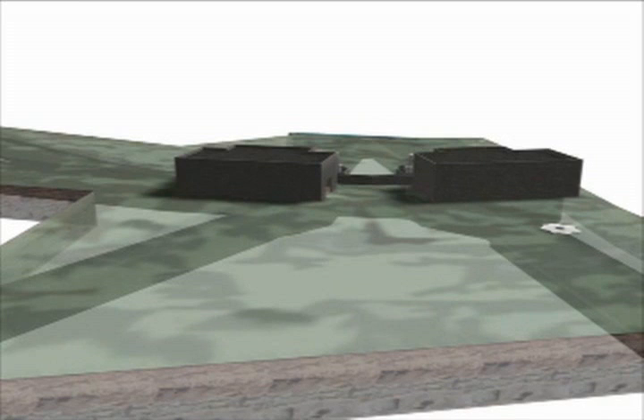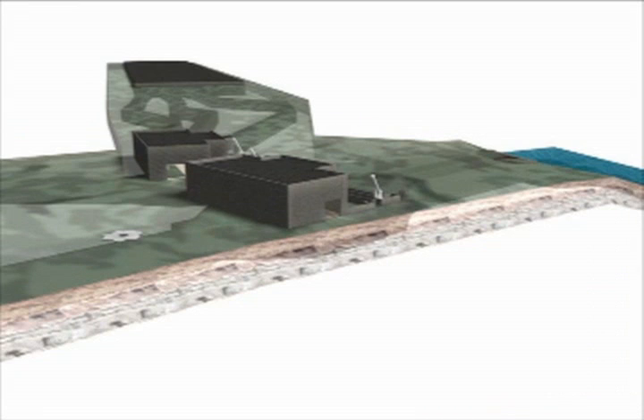The largest regulator is the Shockoe diversion structure. The function of a diversion structure is to receive incoming flow of storm and wastewater and distribute it to appropriate systems depending on the conditions. Beneath the diversion structure is a highly sophisticated system of tunnels. The velocity reducers help to slow the flow of incoming storm and sewer water and trap debris.